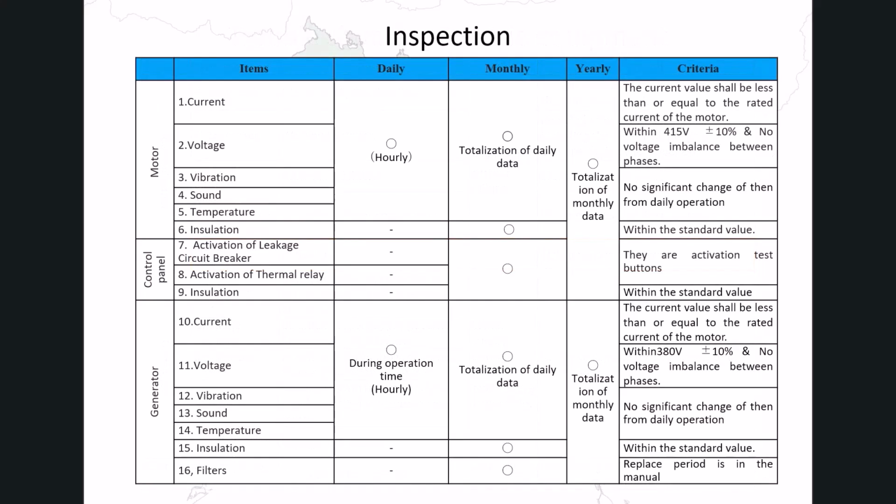This is an inspection sheet introduced in the manual. An inspection sheet shows what data should be recorded routinely for the purpose of appropriate operation and maintenance. Each item listed here corresponds directly to the confirmation points explained earlier. By checking these regularly, you can detect abnormalities before they become serious, or identify the cause of the problem, which will contribute to taking quick actions for countermeasures.